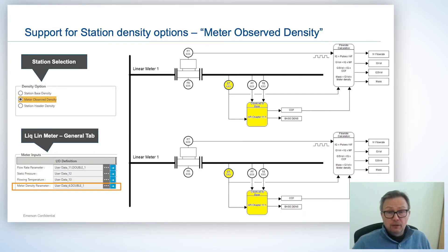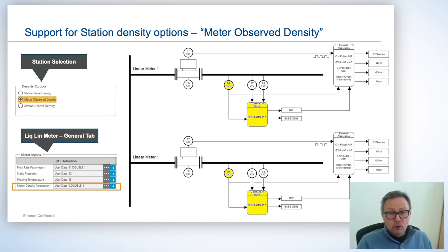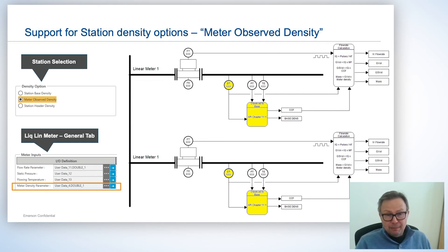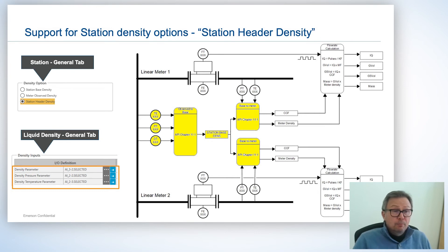Meter observed density is really the option we would use with a Coriolis meter, where the meter itself is not only giving us a flow rate but also giving us a density at the same pressure and temperature as the flow meter. So that's typically used in Coriolis meter applications.